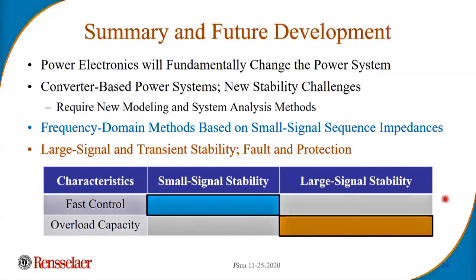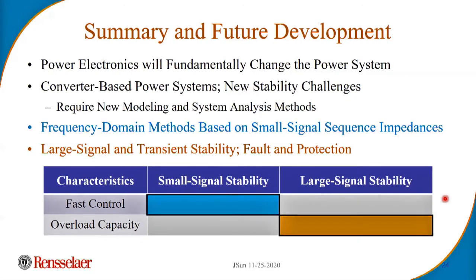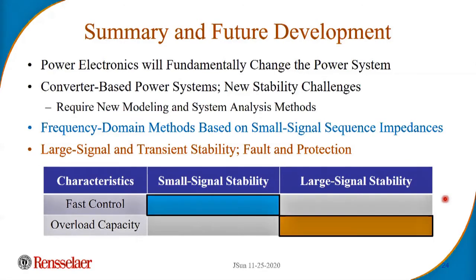So where the industry is seeing now is the frequency domain method we talked about will be the starting point. You can run pre-screening of a very complex network very quickly because it's fundamental. When you have these models, you can run thousands of scenarios overnight. It's really quick, right? A single desktop can run that. Most of the time you will be okay, but if you identify marginal cases, then you can go to more detailed EMT simulation that may give you more confidence, right?